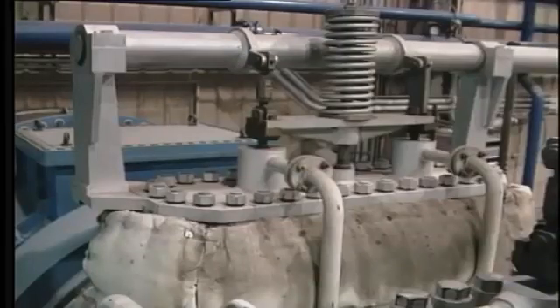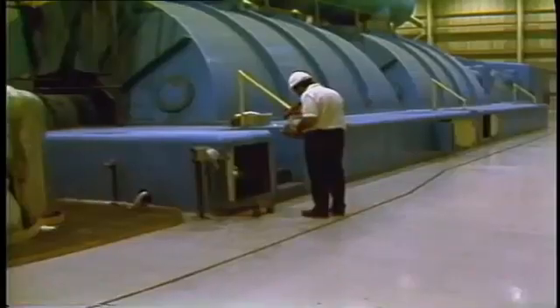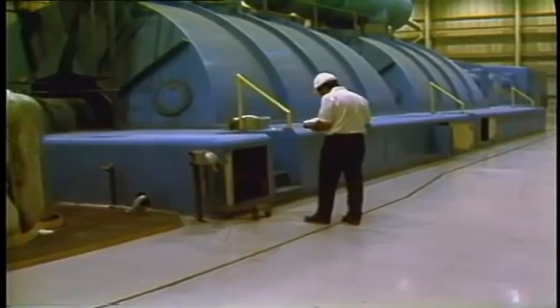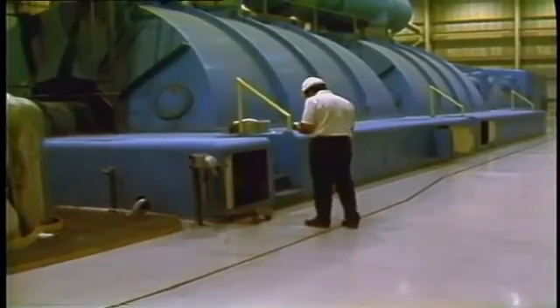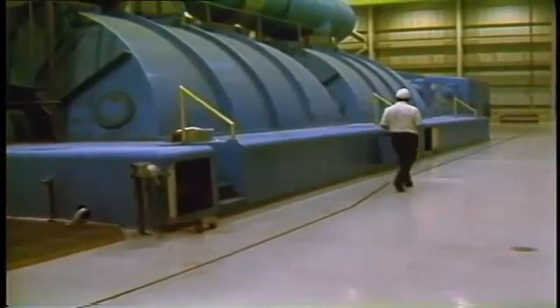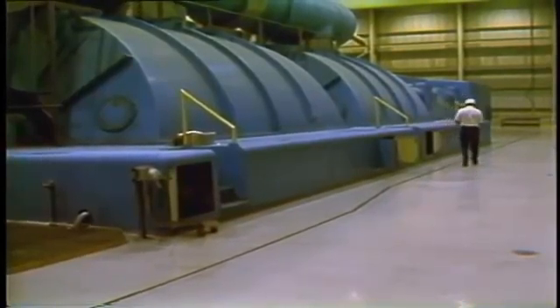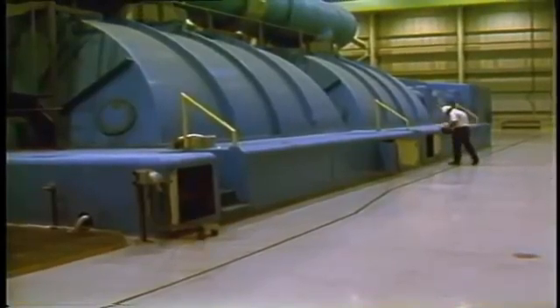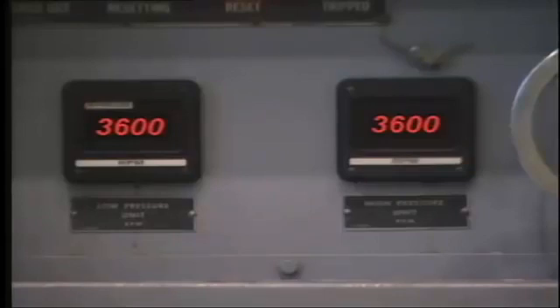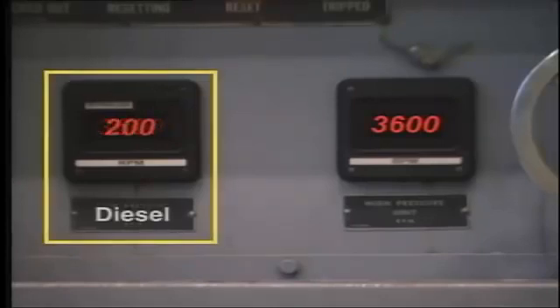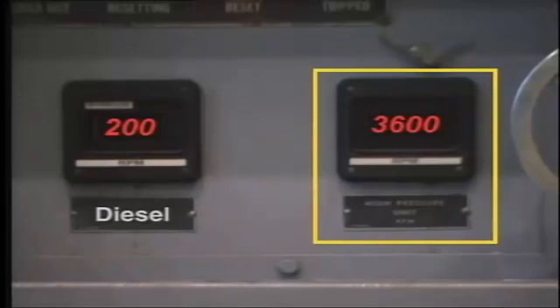The moving parts are the rotor, which drives the generator, and the steam control valves and control gear. The amount of vibration produced by a steam turbine generator and transmitted to the surrounding area is relatively low, provided the machine is in good condition and is correctly installed and aligned. This makes for a quieter operating plant, particularly when compared with the diesel engine or even the gas turbine. The steam turbine runs at high speed, usually 3,600 RPM in North America or 3,000 RPM in Europe, and can therefore be coupled directly to a two-pole generator. The diesel engine operates at around 200 RPM, so the specific output of the steam turbine is much greater.